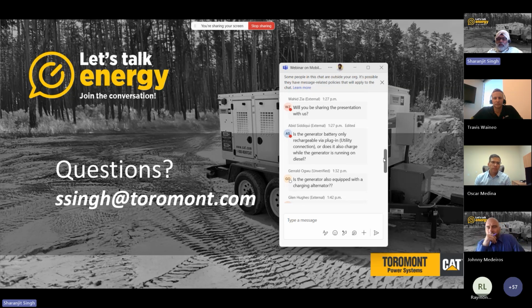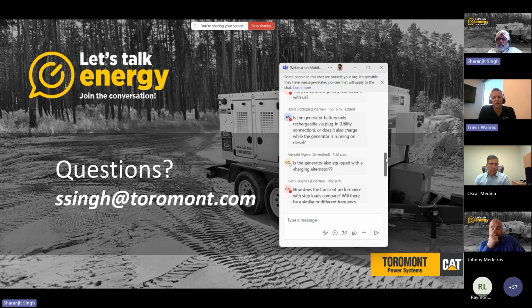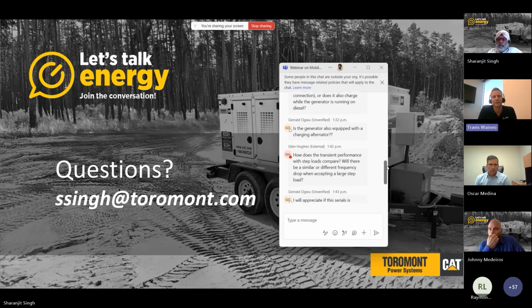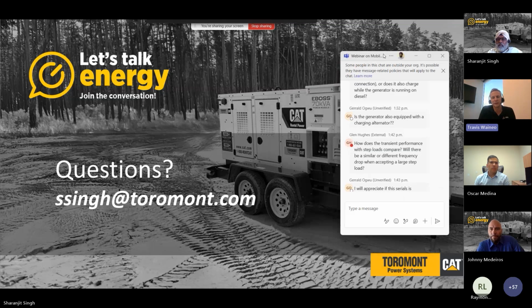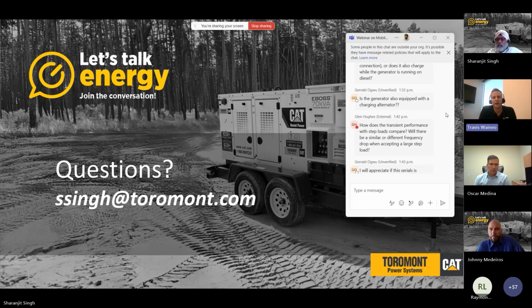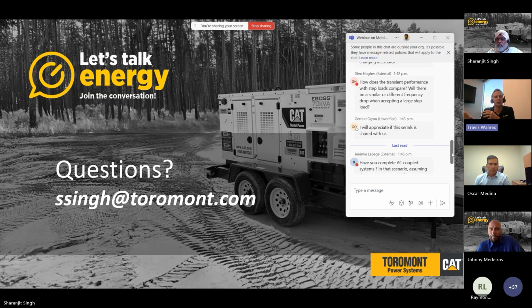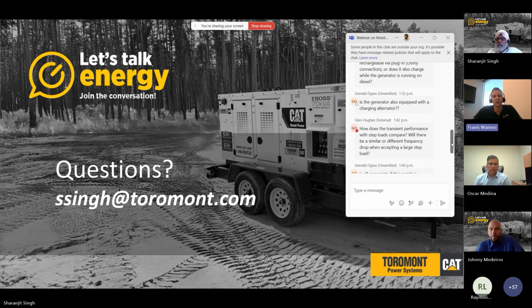Next question: is the generator battery only rechargeable via the plug utility connection, or does it charge while the generator is running on diesel? Since this is a hybrid, we are mainly charging it on diesel. Plug in that diesel generator and it'll charge on that. You can also use a 480 volt grid connection to recharge, but we're really optimizing this to work with a diesel generator, so it recharges using the diesel gen while still discharging. A lot of times people ask, can you still run the output while you're charging it? In this case it's designed perfectly for that - it fires on the diesel generator whenever it needs to charge the battery, but the output is always consistently on, running off the battery itself.